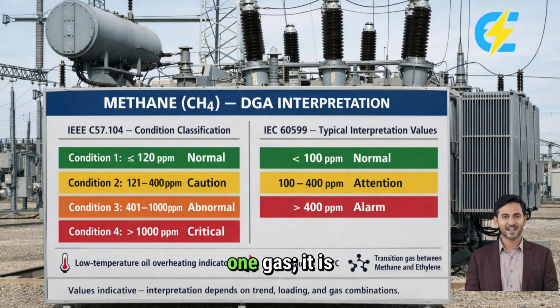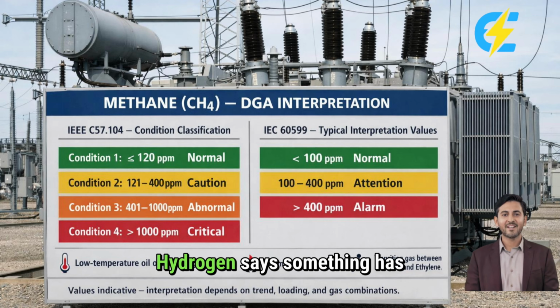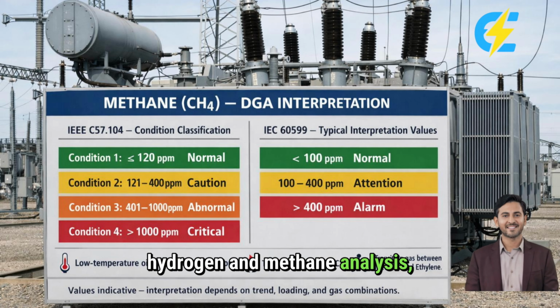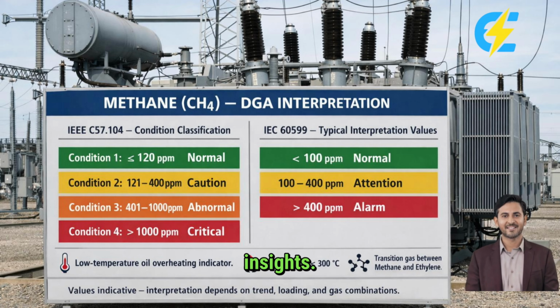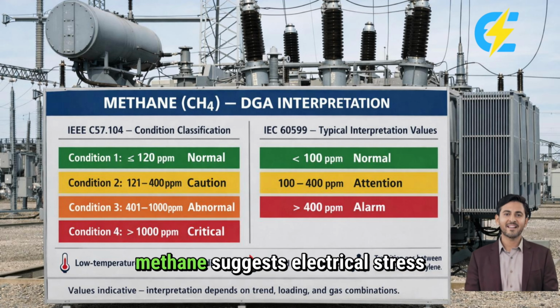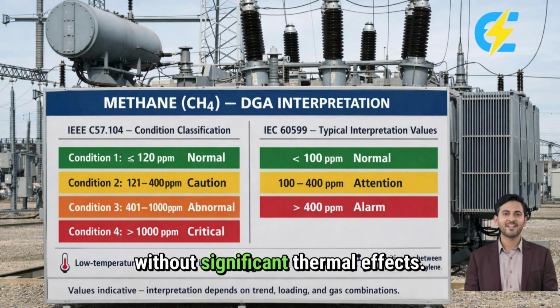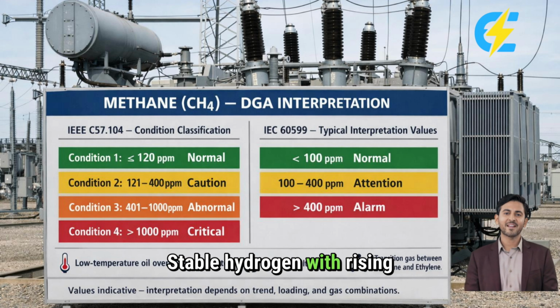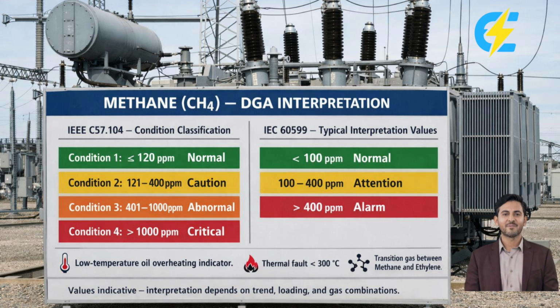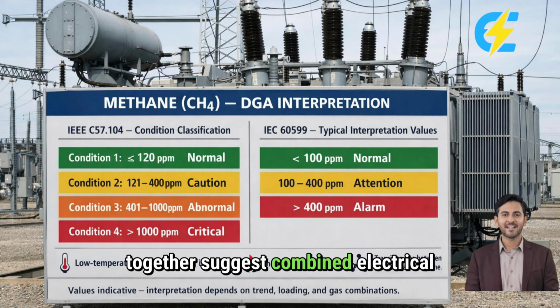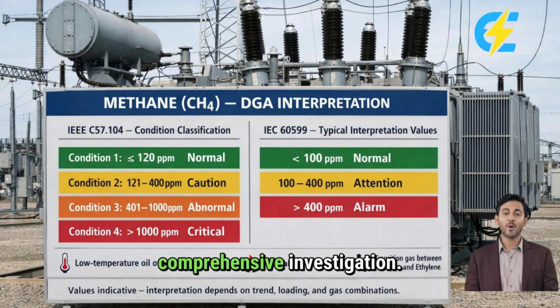DGA is not about one gas, it is about patterns. Hydrogen says something has started. Methane says that something is heat. When you combine hydrogen and methane analysis, you gain powerful diagnostic insights. Rising hydrogen with stable methane suggests electrical stress without significant thermal effects. Stable hydrogen with rising methane indicates thermal stress without major electrical disturbances. Rising both the gases together suggests combined electrical and thermal stress requiring comprehensive investigation. Good engineers monitor, great engineers interpret trends.